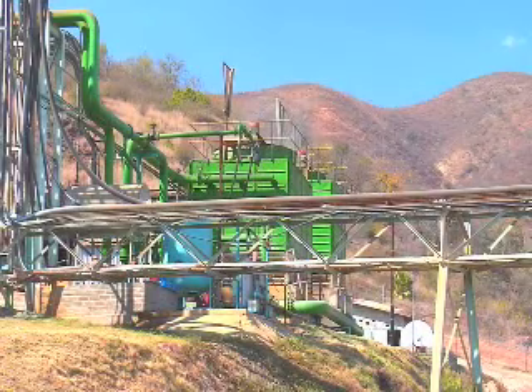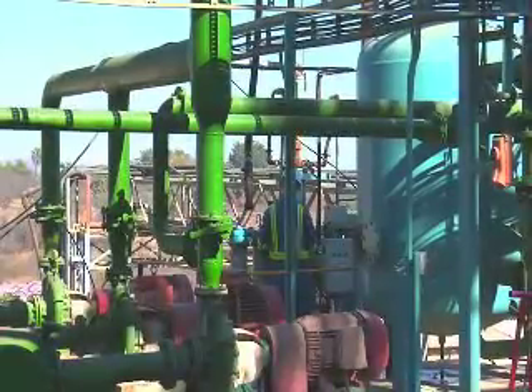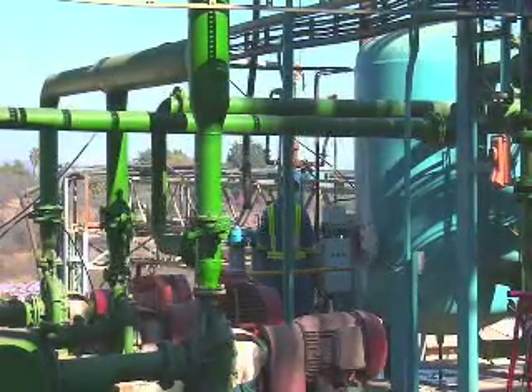In general, we used to use 2 pumps to supply enough water for the whole cooling system. Currently we're only running 1 pump. It's about a 44 kilowatt motor's power that we save at this stage.